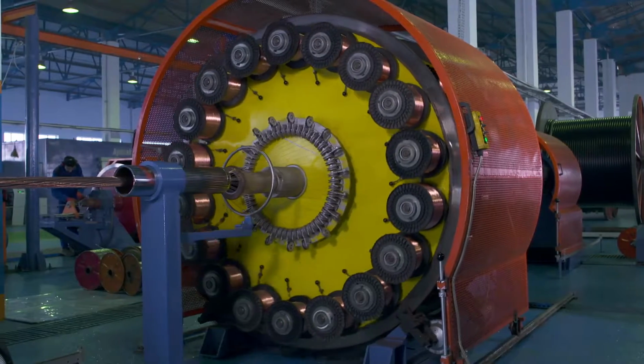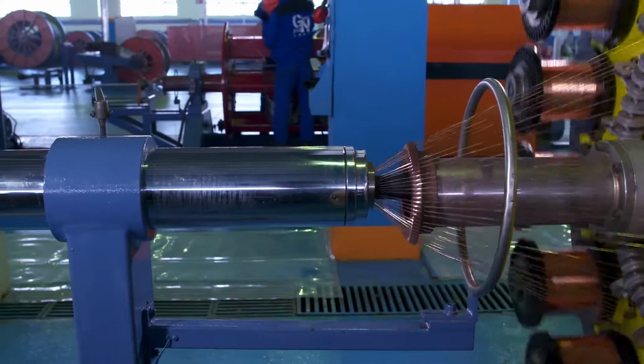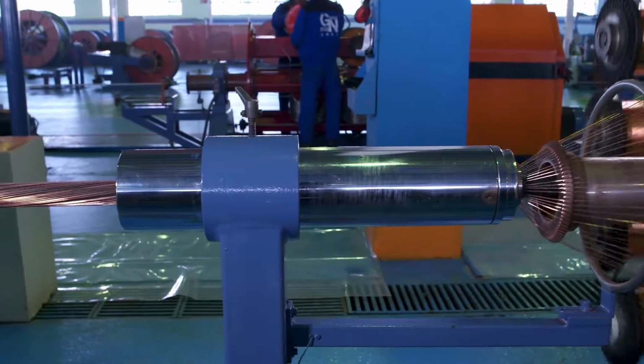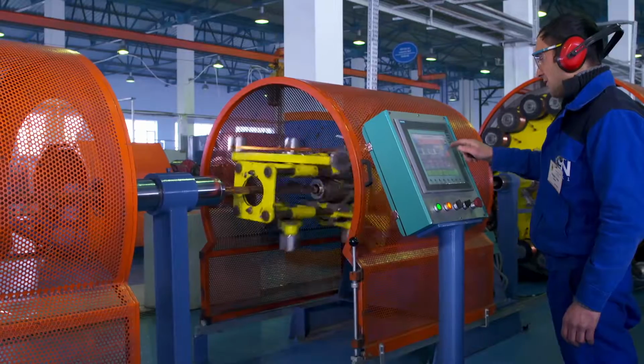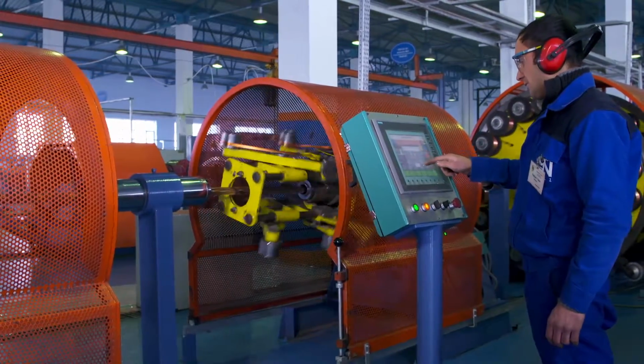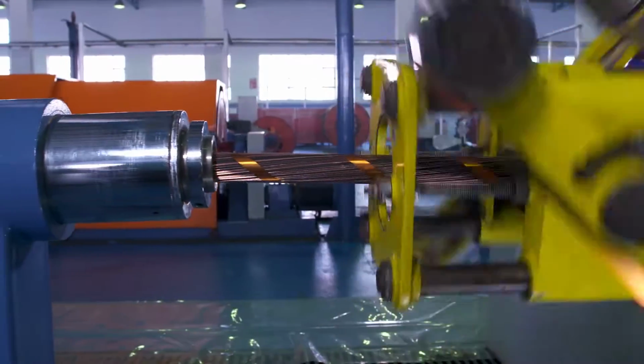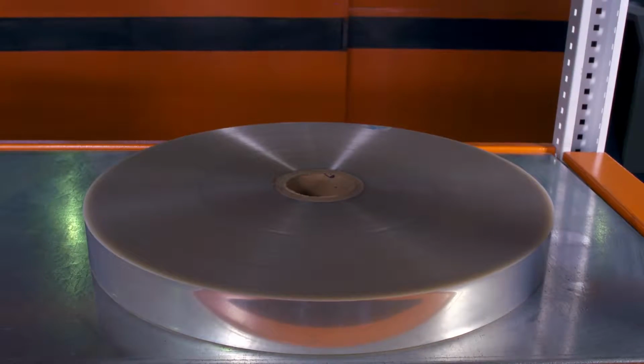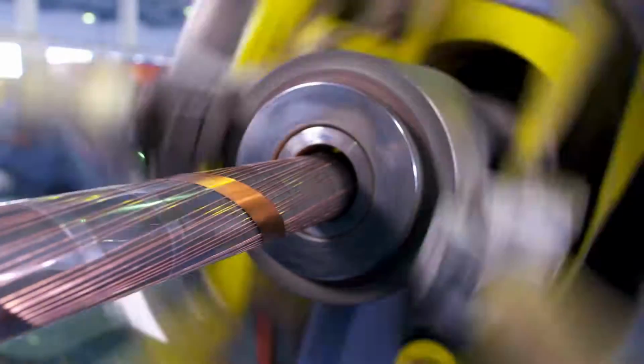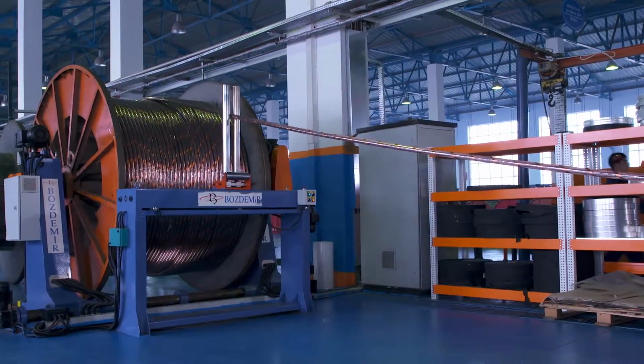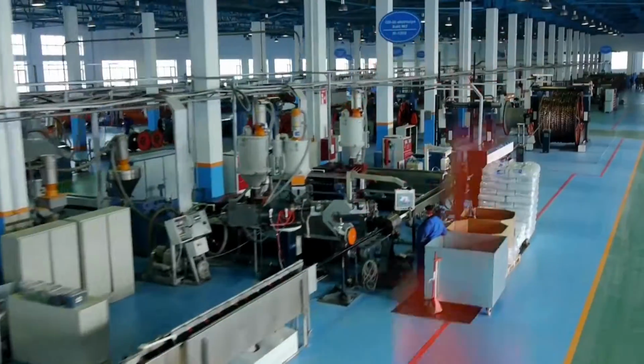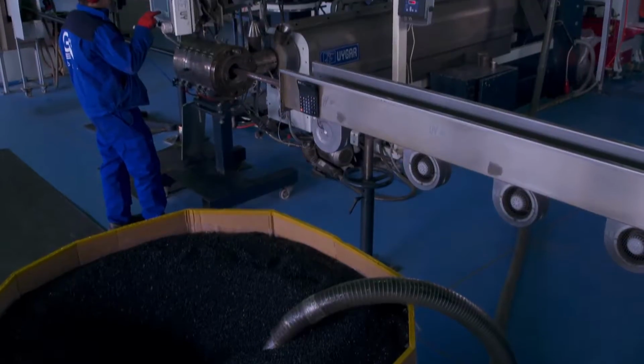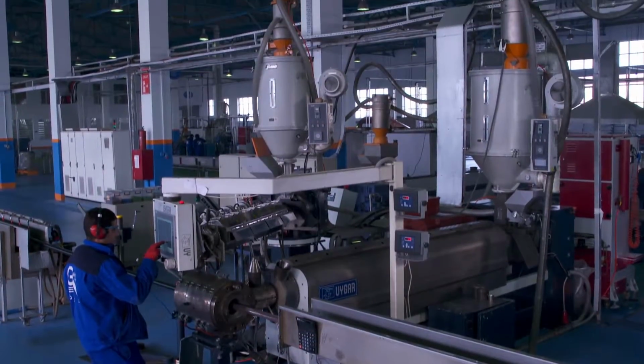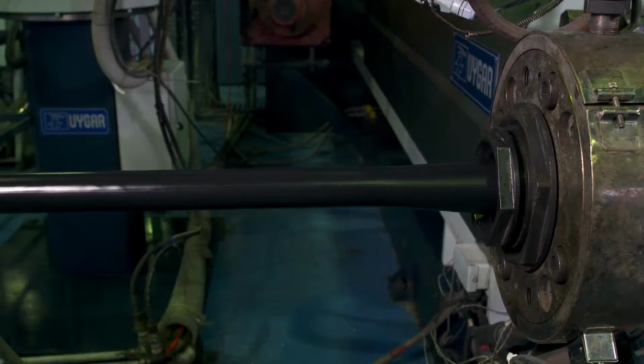Then the copper wires and helically copper tape are applied over the protective barrier layer. The copper screen provides the grounding function. It conducts all fault current to prevent cable damage. The polyester tape could be applied to prevent penetration of the outer sheath plastic between the copper wires over the copper screen. The last step involves covering the surface of the cable with a protective coating by extrusion. Depending on the customer's request, the outer sheath can be made of polyvinyl chloride plastic, polyethylene or fireproof halogen-free material.